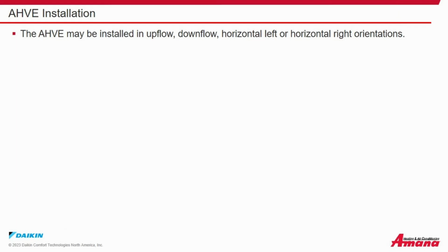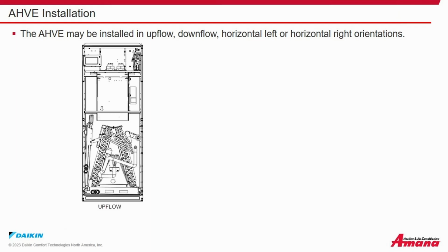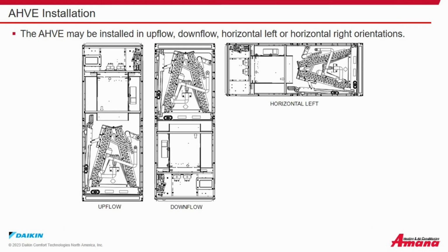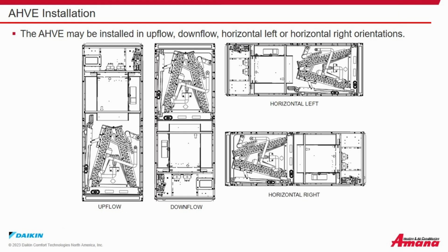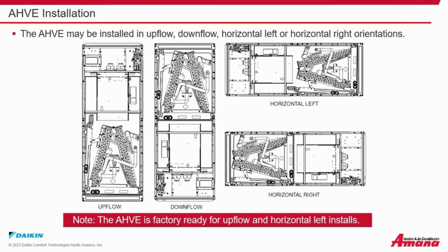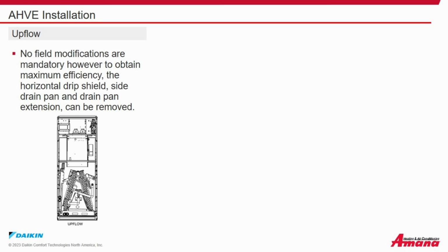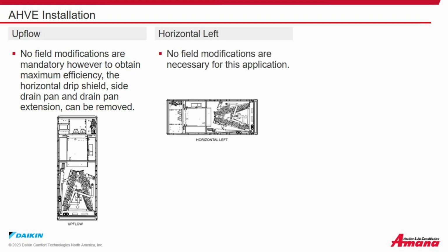The AHVE air handler may be installed in an upflow, downflow, horizontal left, or horizontal right orientation. Note, the AHVE is factory ready for upflow and horizontal left installs. For upflow installation, no field modifications are mandatory. However, to obtain the maximum efficiency, the horizontal drip shield, side drain pan, and drain pan extension can be removed. For horizontal left applications, no field modifications are necessary.